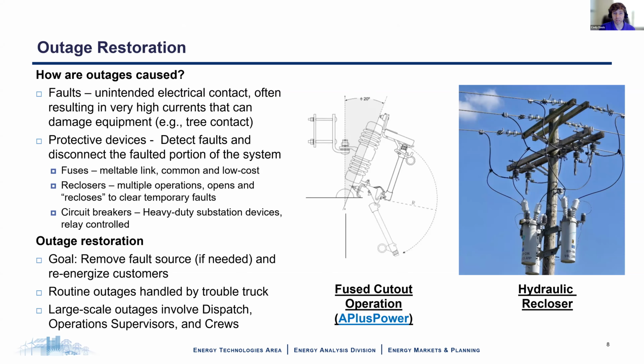Protection devices exist to detect faults and disconnect the portion of the system that is experiencing that fault from the rest of the sort of healthy system. This is accomplished by physically making an open point and disconnecting that section of the system. We have a couple of different technologies that can do this. We have fuses, which is sort of pictured there in the middle. There's a fuse link inside that little barrel. This whole assembly is called a fuse cutout. What happens is when there's a fault, the fuse blows and that barrel will physically swing down in an arc to indicate that something bad has happened downstream of that device. So it helps people troubleshoot.